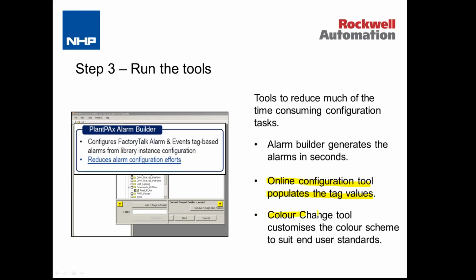The final one that we can see here is a colour change tool. So the library is configured around the current best practice in HMI, which is a grayscale approach. You may know it as ISA 101 or abnormal situation management implementation. They both are working to the same end result, an HMI screen that just attracts the operator to the areas that need attention. So we have very little colour on the screen unless there's an alarm action or something that the operator needs to respond to.